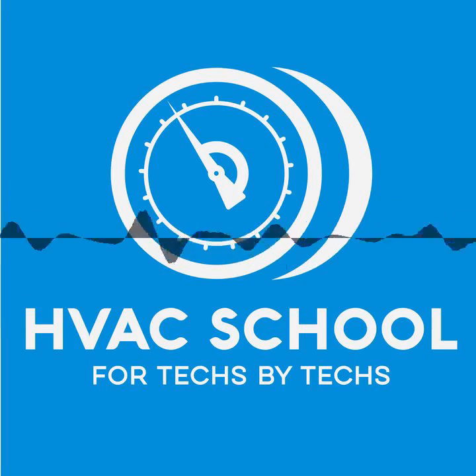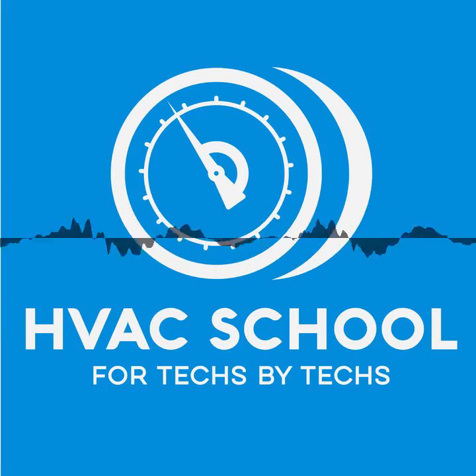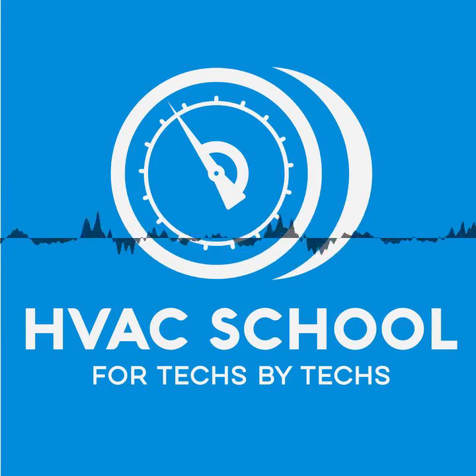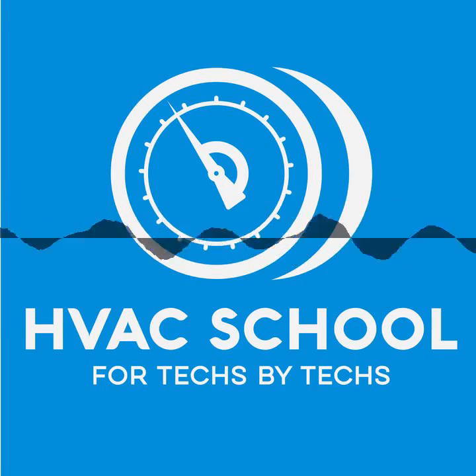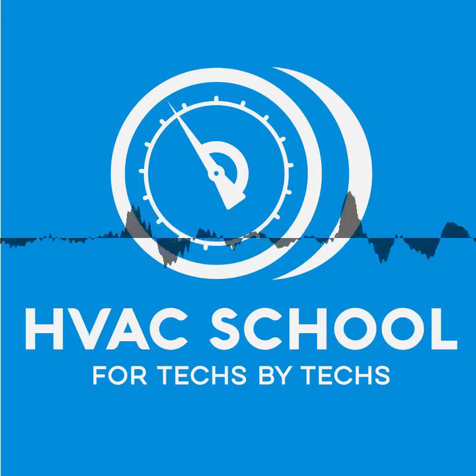And this is where the whole systematic troubleshooting, as you mentioned earlier, comes in. Very rarely is the TX valve itself the source of the problem. Rather, it's just the collector of dirt, the thing that's feeding the evaporator that's closest to where we're picturing a problem. So I get that part 100%. So maybe we can spend some time going through, yes, we'll talk about TX valves and best practices, but let's look at some of the other things that may be causing problems that aren't the TX valve.